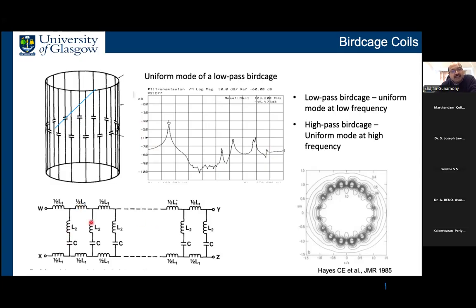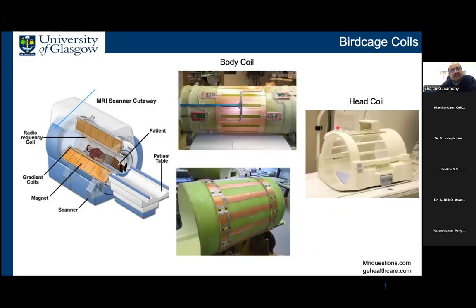And here, this is an equivalent circuit of a birdcage coil. So it's made of inductor in series and then a capacitor in shunt. Here you can see a contour plot of the field produced by this birdcage structure. As I said, it has uniform current, so it will produce a uniform field, as you can see here. So here are some examples of birdcage coils. In the middle, these are body coils. These are fairly large structures. They're about 80 to 90 centimeters in diameter and about 1.5 meters long. So these are typically hidden behind the cover of the magnet. You don't see them outside.